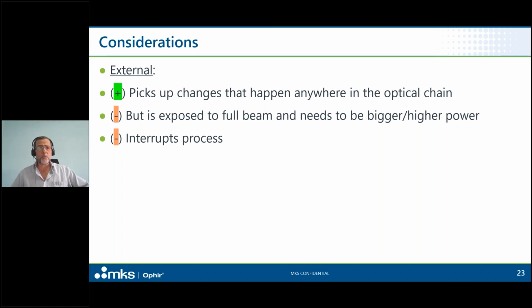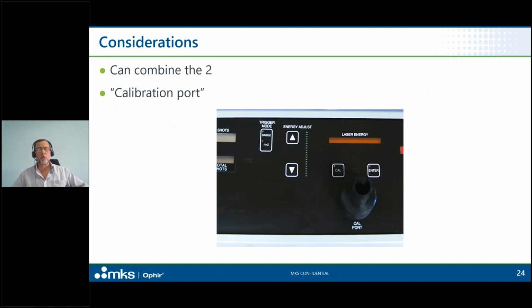I've seen many customers who found a pretty elegant way of combining these two and getting the best of both worlds. What they've done is they have a small sensor built inside the system looking at a small percentage of what's coming out of the laser. And that's ongoing because it's not interrupting the beam. And at the same time, on one of the side panels of the system, they have an opening that they call a calibration port, a cal port. And inside that is a full power sensor that measures the full power of the beam, either before each procedure or once a day or whatever, depending on the details.